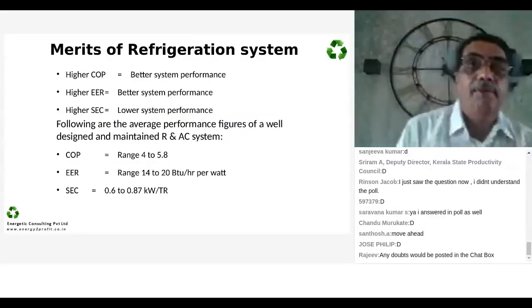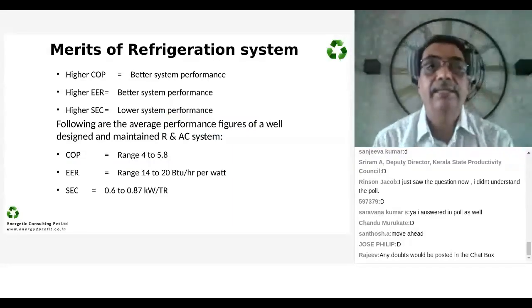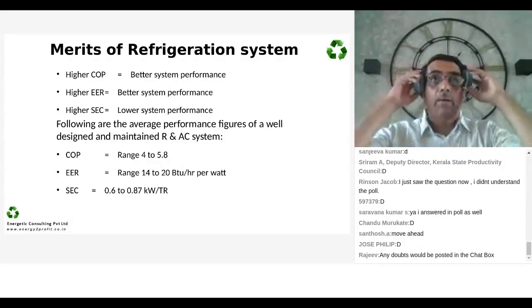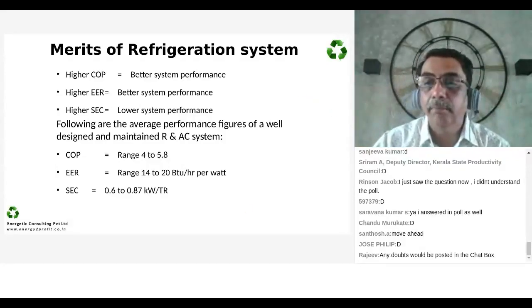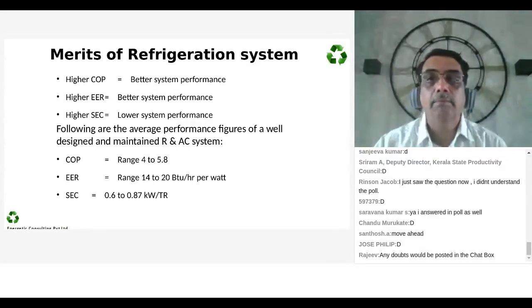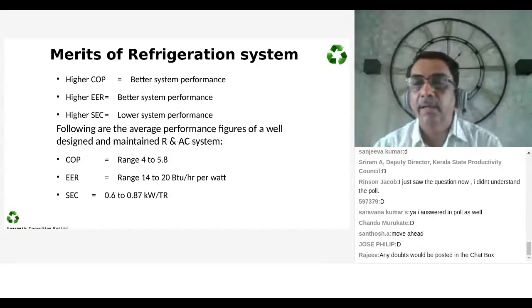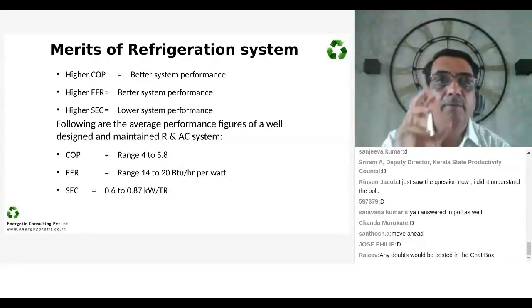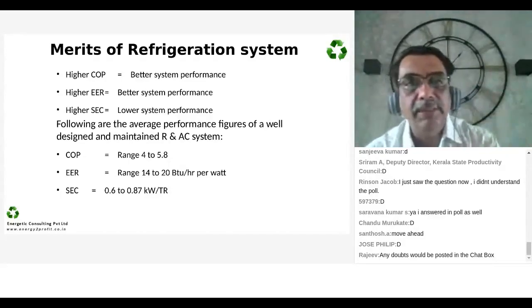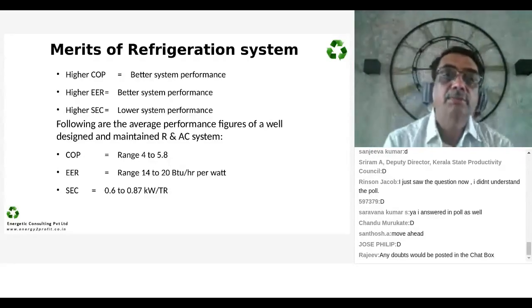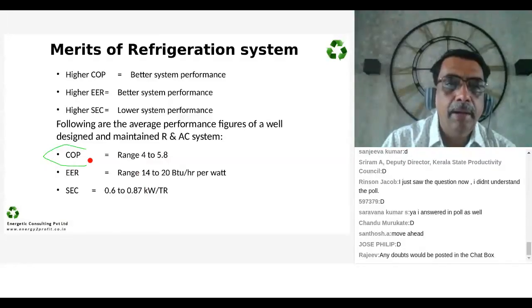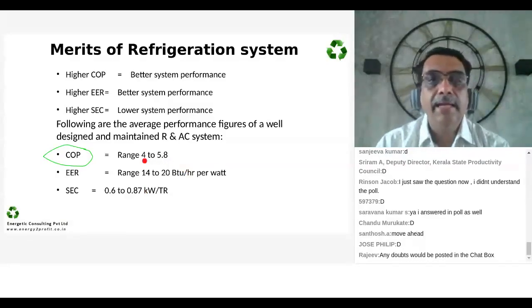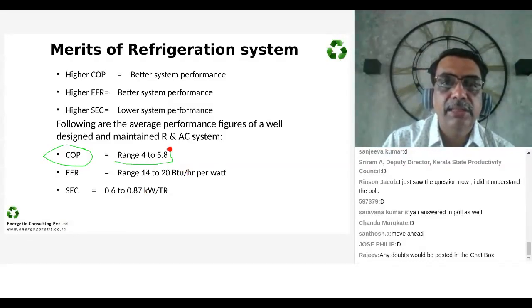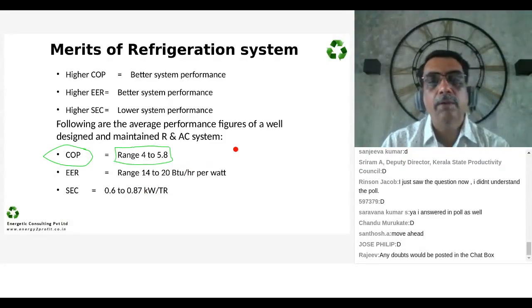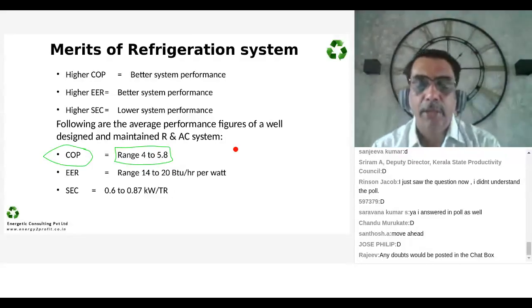How is air conditioning system energy efficiency measured? Now, I'm sure all of you would be listening to these typical jargons, let me put it that way. Jargons are like coefficient of performance, energy efficiency ratio, specific energy consumption, ACC. So what does it mean? Coefficient of performance is a number which has got no units, and it tells you how efficient your system actually is, on the input and output, percentage of output as input.